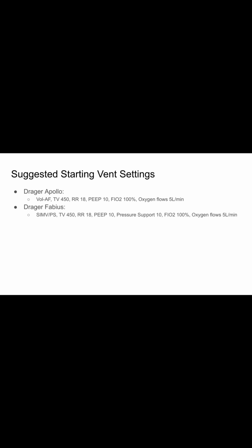So for the Apollos, we're recommending the volume autoflow mode with a tidal volume of 450. Obviously, we'll try to do lung protective ventilation with lower volumes of 6 to 8 cc's per kilo. But if you don't have time to calculate, 450 is a safe bet for most people. Respiratory rate of 18, PEEP of 10, 100% FiO2, and then set your oxygen flows to 5 liters a minute, which is what we will recommend as a minimum flow for all patients in the PACU ICU.